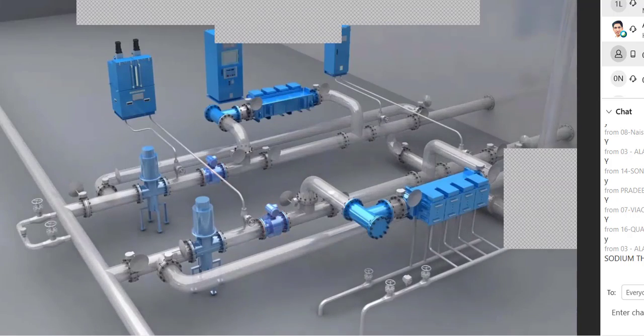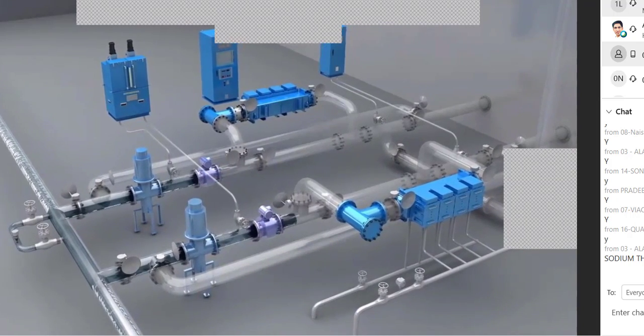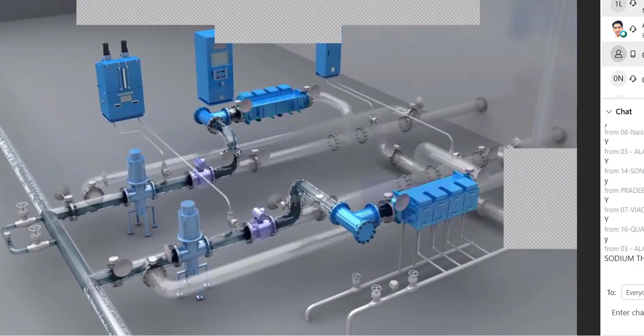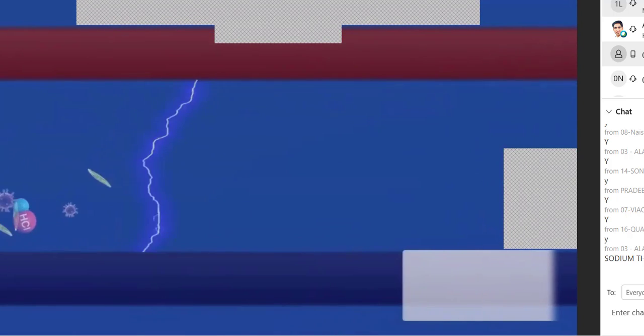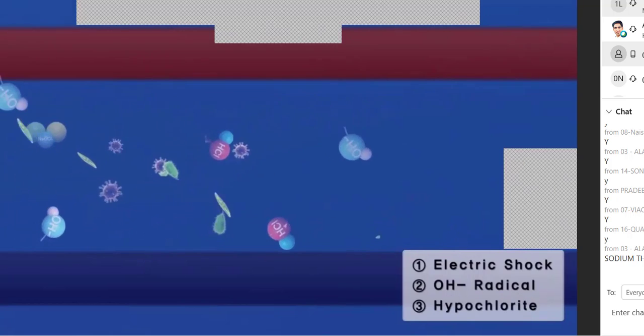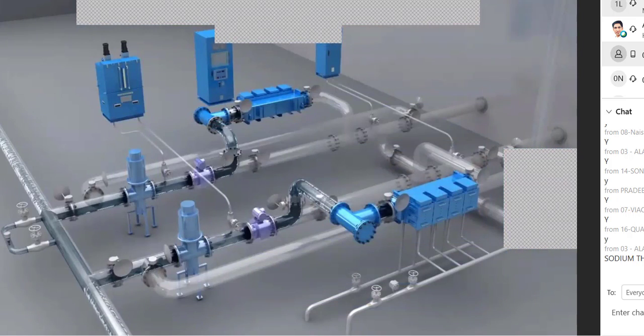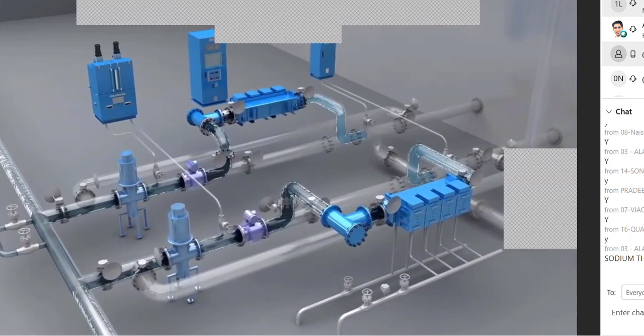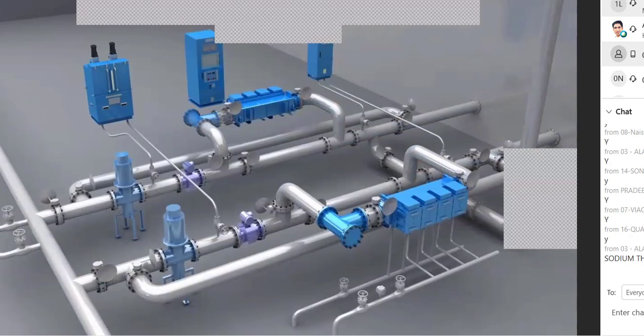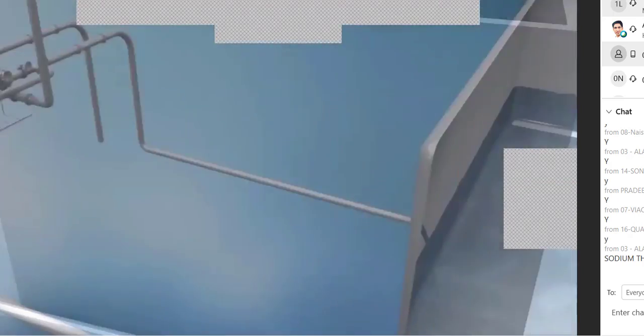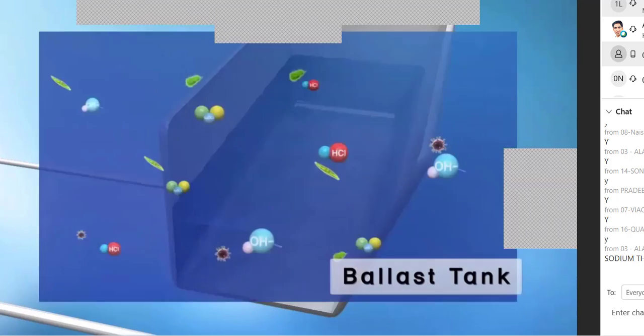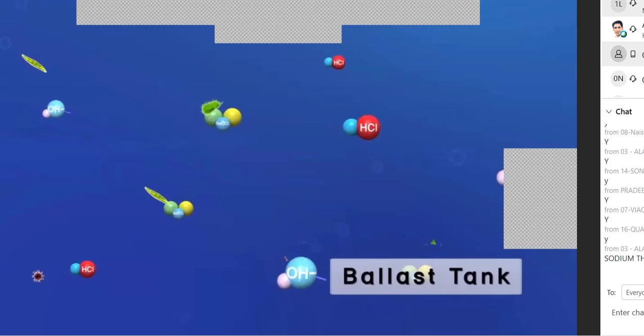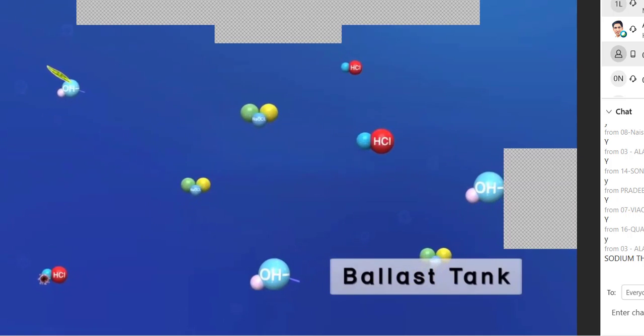As the ballast water flows in the vessel, ECU is receiving the required current and voltage from the rectifier, enabling them to electrolyze the ballast water and kill microorganisms by electrochemical actions. The electric energy and the production of oxidants such as hydroxyl radical and hypobromite can oxidize cell membranes and cell walls to disinfect organisms. After treatment, the treated ballast water is stored in the ballast tank during the voyage. During this period, TRO, the residual hypochlorite, remains active in the ballast tank, preventing any regrowth of microorganisms for up to 30 days after treatment.